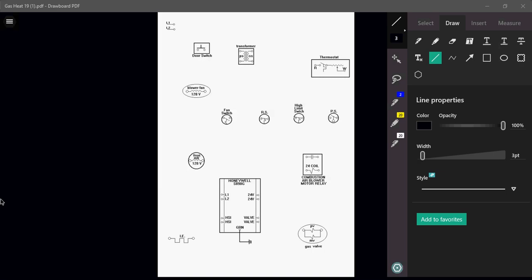So how are we going to wire such a system? Well, here we go. Again, here's another pictorial diagram of a standard simplified hot surface ignition furnace. Okay, so we have our L1 and L2, which is our power source. We have a door switch, transformer, thermostat, a blower, fan switch, our safeties here, pressure switch, high limit switch, rollout switch. We have our vent motor, which is again our inducer motor. We got our combustion air blower motor relay, which is what controls our vent motor. Obviously, it's operated off of a 24-volt coil. Here is our igniter, or ignition element, sometimes that's what they're called in diagrams. And then you have your gas valve.